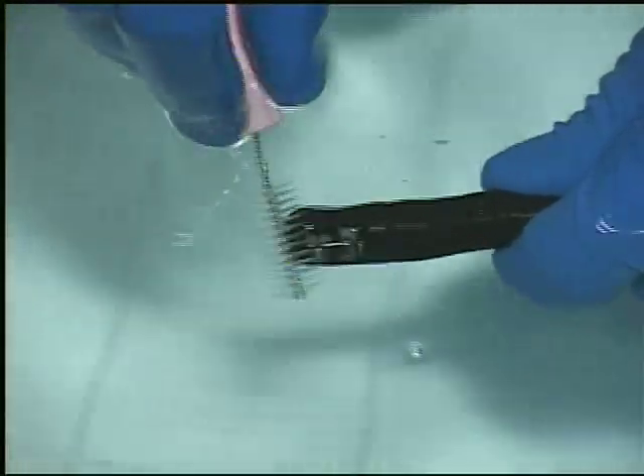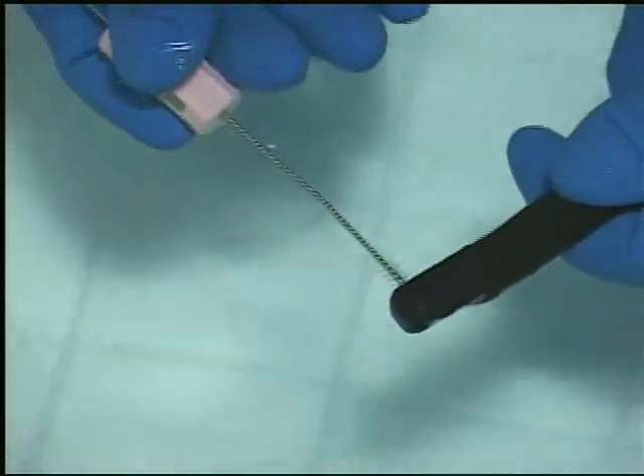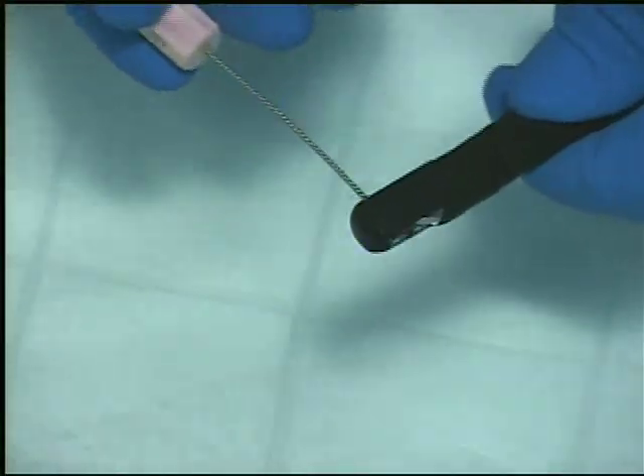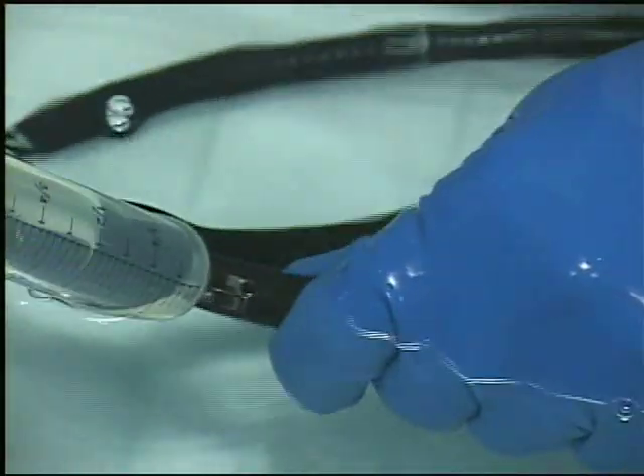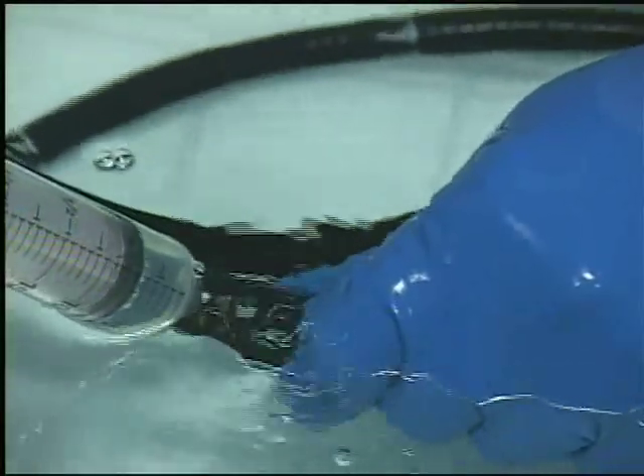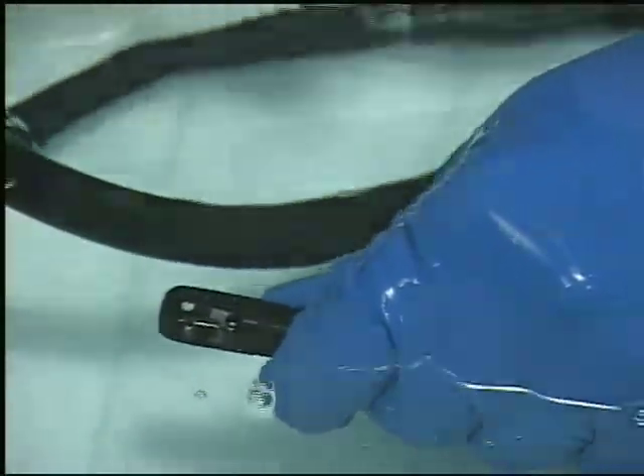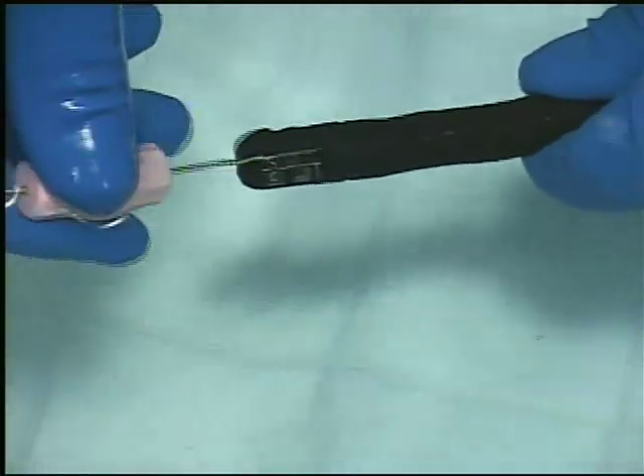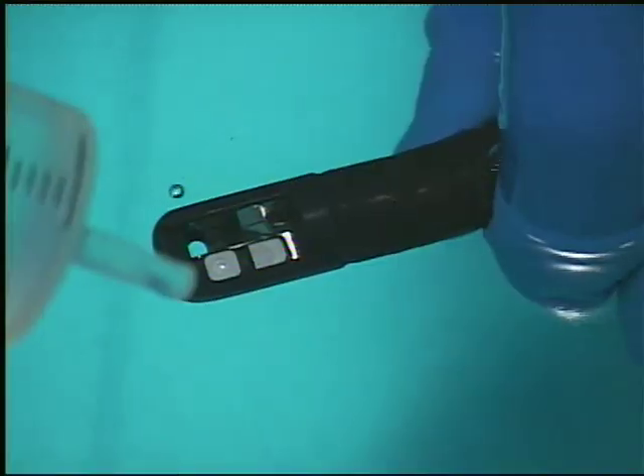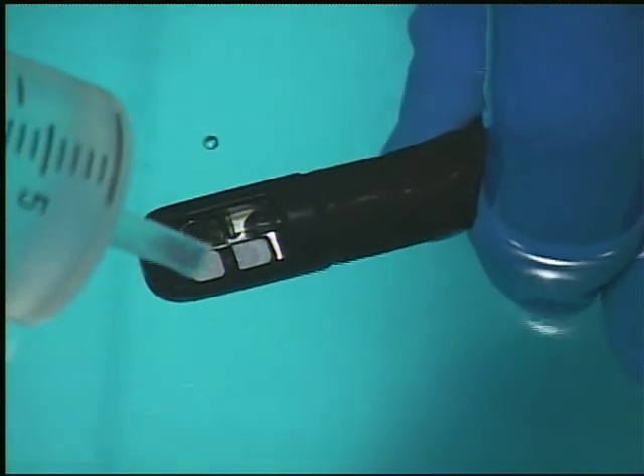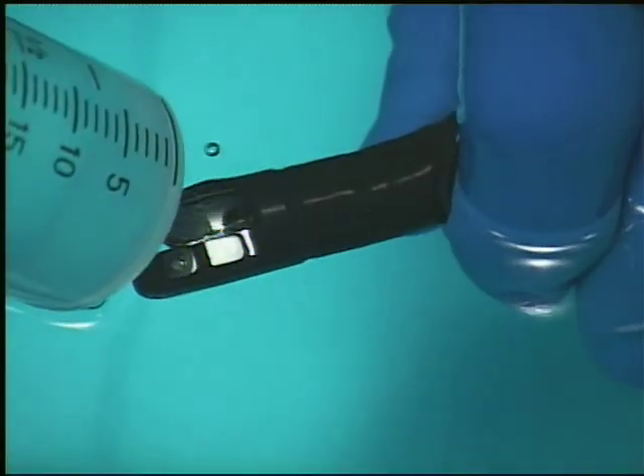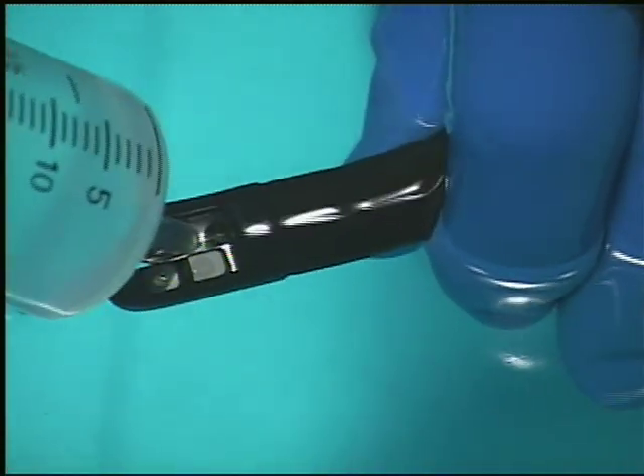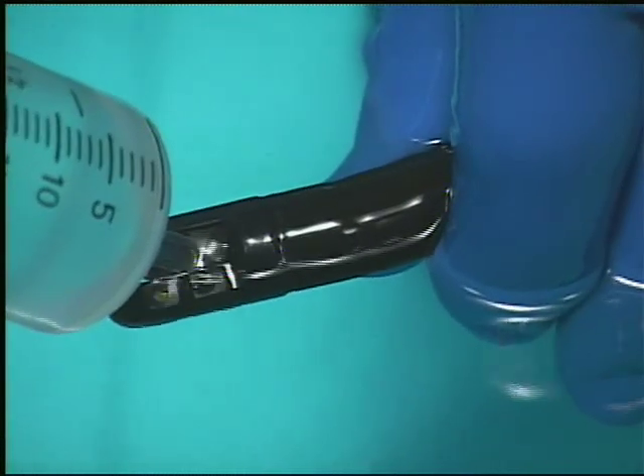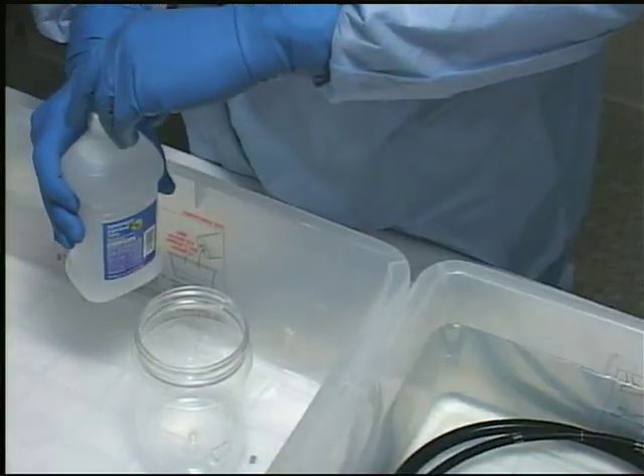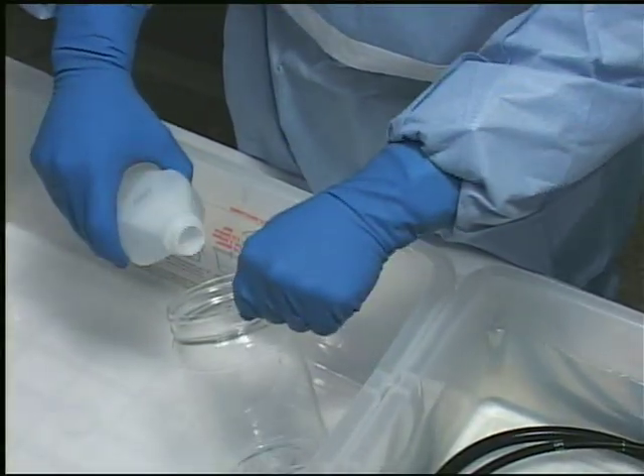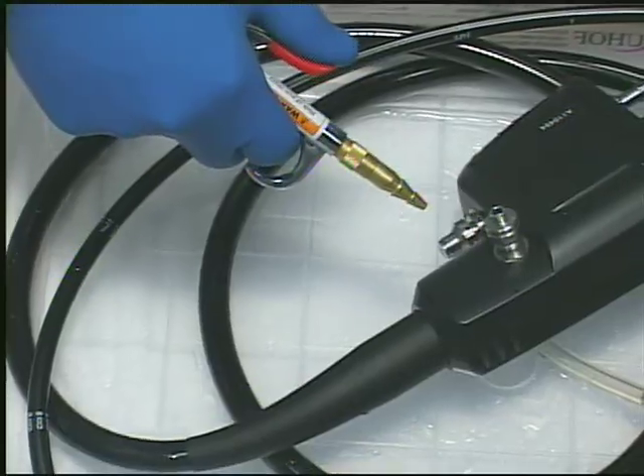All areas surrounding the elevator mechanism should be brushed clean and exposed first to an enzymatic detergent and then to a disinfectant. Syringes should be used to flush reprocessing solutions directly behind the elevator. All accessible internal channels should be cleaned by brush and then exposed to a detergent solution for a time period recommended by the detergent manufacturer. After rinsing and drying, all internal channels and external scope surfaces should be exposed to a high-level disinfectant, rinsed, and dried again. This in turn must be followed by a final alcohol rinse and forced air drying of the channels at no greater than 24 psi.